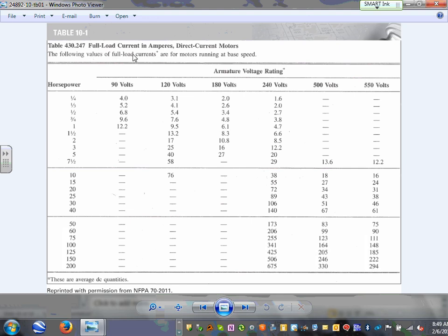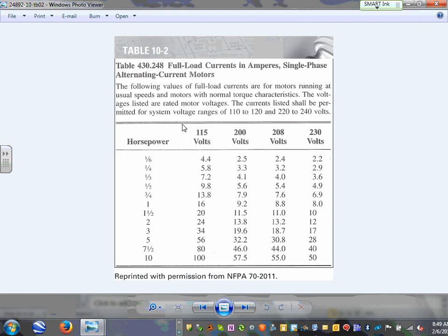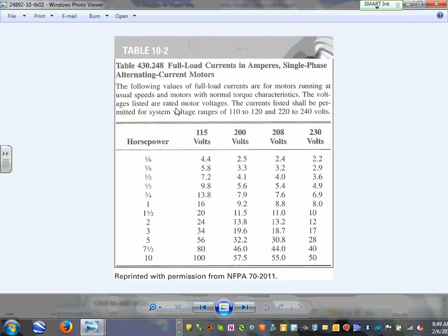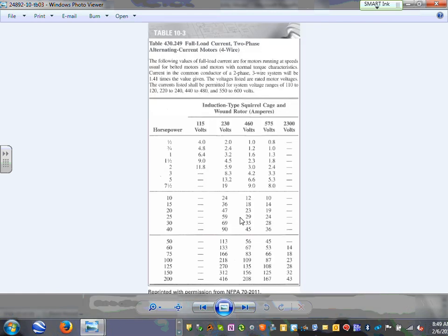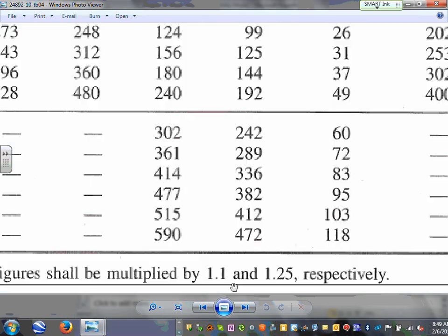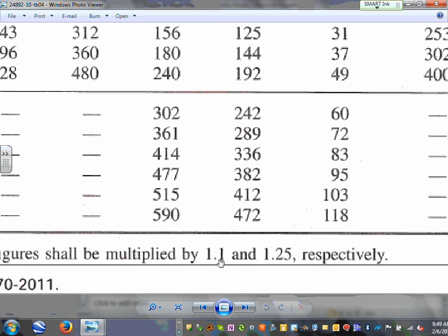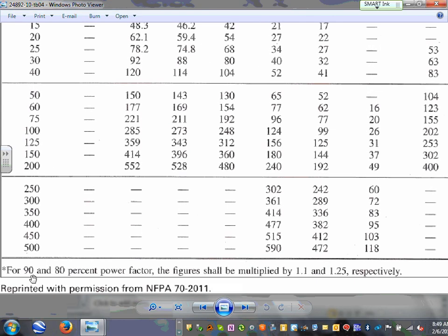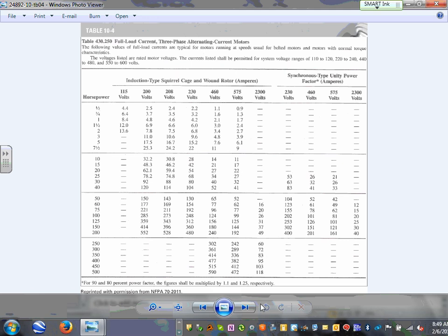The tables used in this chapter include full load amps for DC motors, single-phase motors, and three-phase induction motors. At the bottom of the three-phase table you'll find multipliers of 1.1 and 1.25 for synchronous motors at power factors of 90% and 80% respectively.